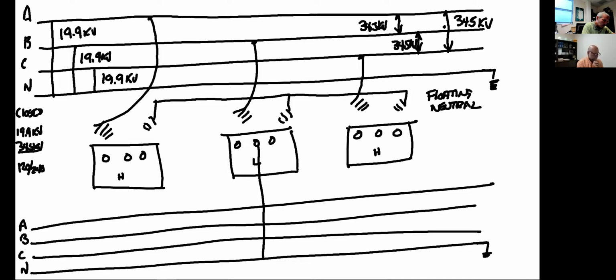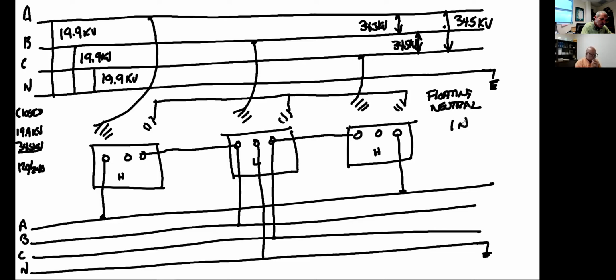Neutral. This is going to go down to B, connect. This is going to go down to C, connect. All right. What do I need to do in between transformers? What am I missing between here and here? Tie-in butts, both directions. Now I have 3 transformers total. Tie-in butts both directions. My high leg is now going to come out here to A, and this high leg also comes to A. That makes it 1 conductor. So I've satisfied 1 neutral and 3 hot legs. Okay. Remember now, A is the high leg.